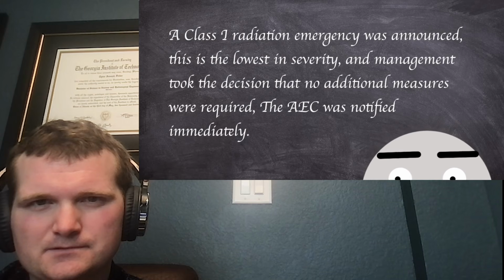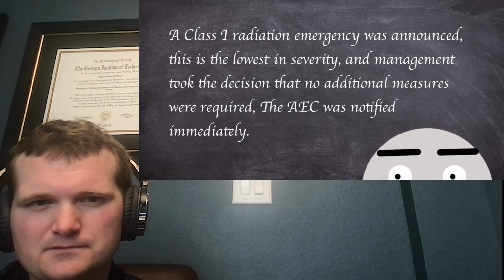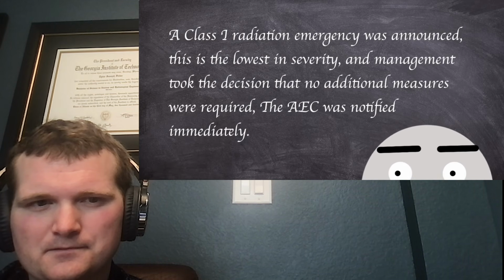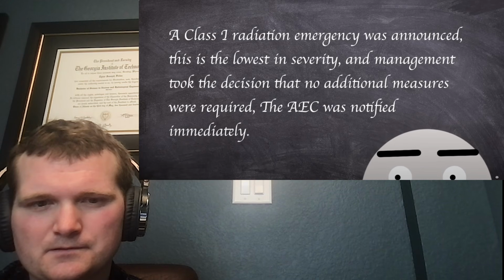The power of the reactor was quickly reduced to 3.3 megawatts as operators scrammed the unit. The containment building was automatically isolated, although there was no one inside. Reduced to... wait a minute, so reactor power should go all the way down. Is he talking about there's 3.3 megawatts of decay heat left? At the time, a Class 1 radiation emergency was announced. This is the lowest in severity, and management took the decision that no additional measures were required. The AEC was notified immediately.